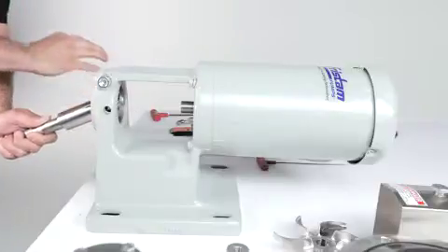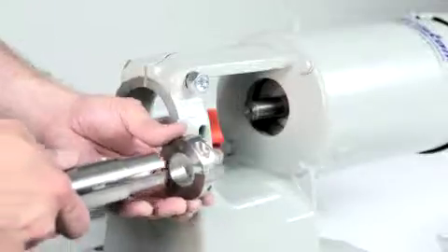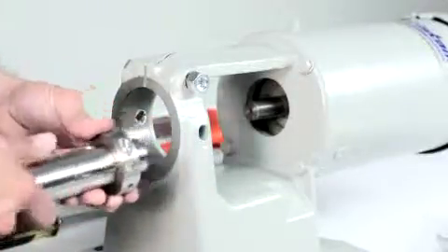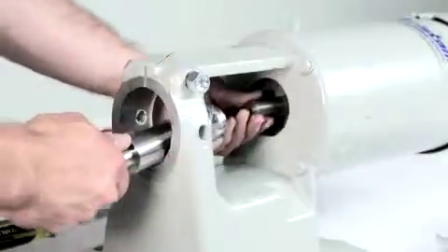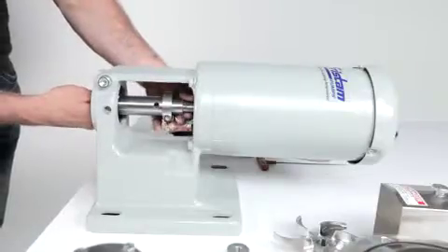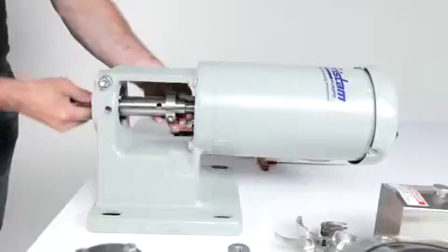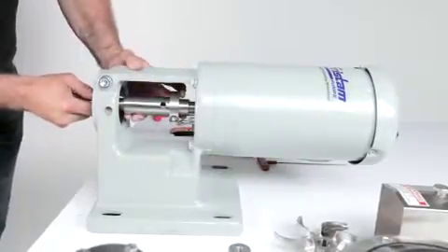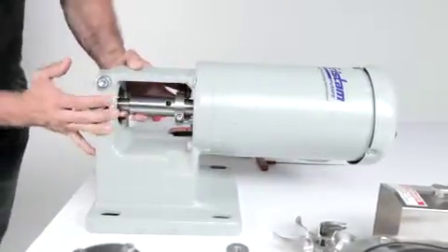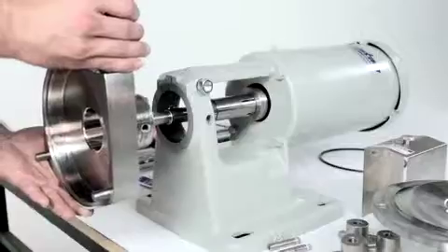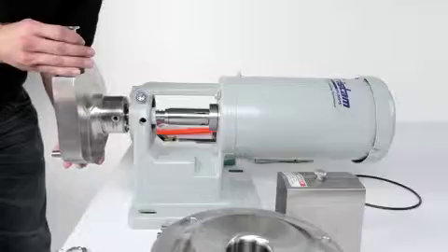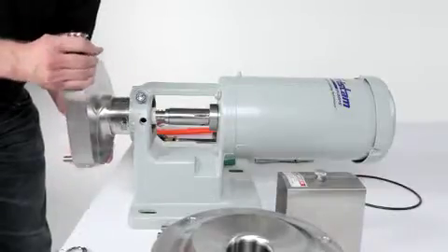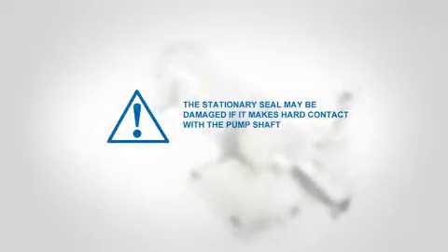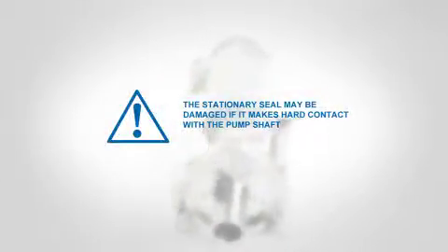To install the new shaft, align the slot of the clamping ring directly over the slot on the shaft. Then slide the new shaft collar onto the pump shaft, but do not tighten the shaft collar screw at this time. Slide the pump shaft and shaft collar onto the motor shaft. Carefully slide the pump housing over the pump shaft and back against the flange support. The stationary seal may be damaged if it makes hard contact with the pump shaft.